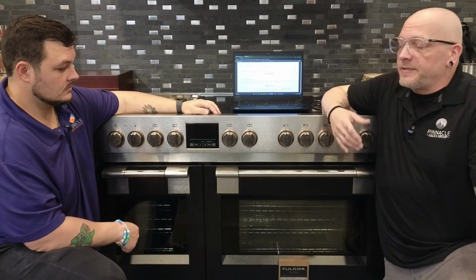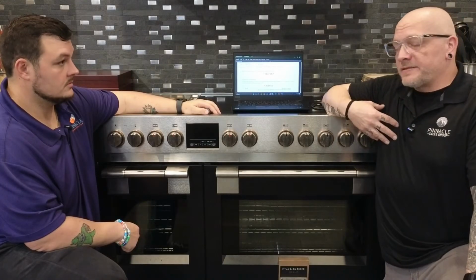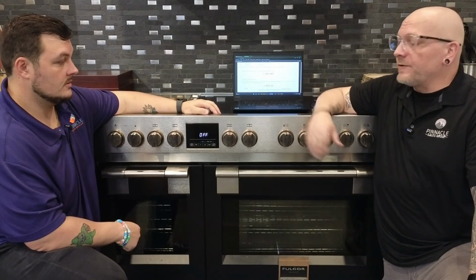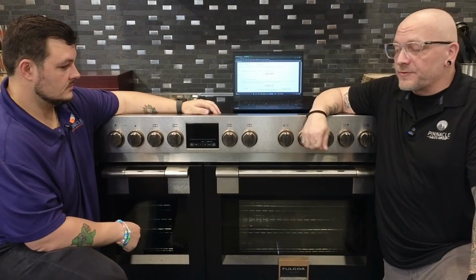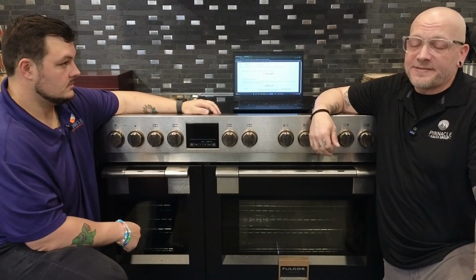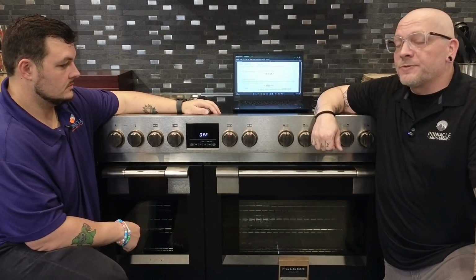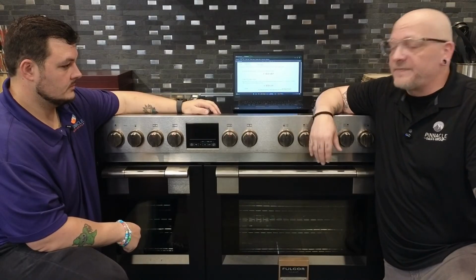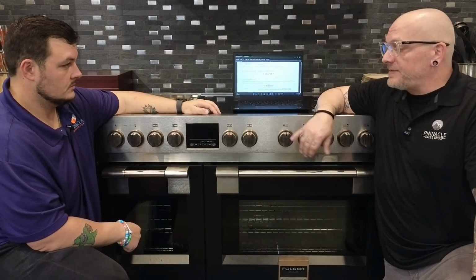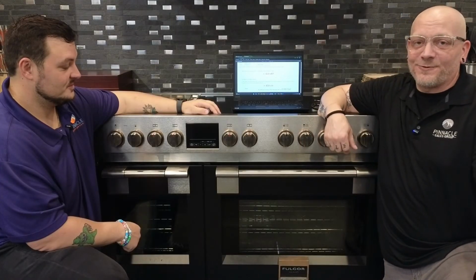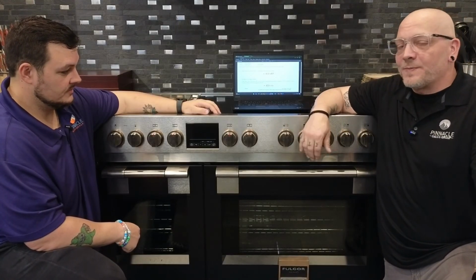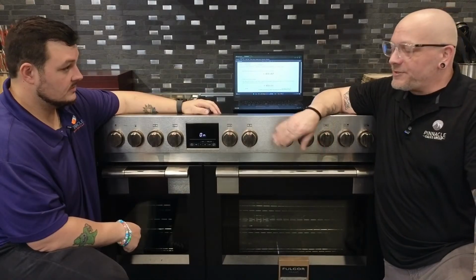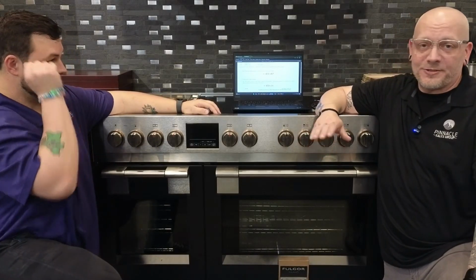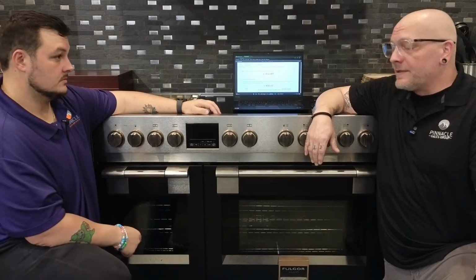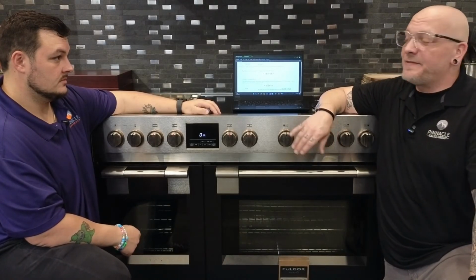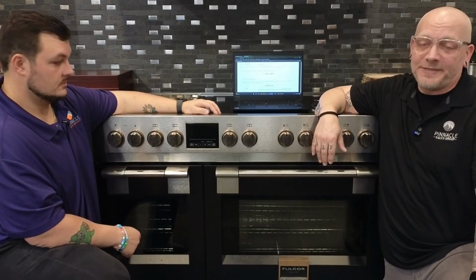Using this test is a great resource. Being a technician for over 25 years, pulling out a 48-inch range to put my meter on the terminals for that temp probe just to ohm it out and check the resistance, when this machine can do it for me with a couple buttons, is a lifesaver. Save your knees, save your shoulders, save the customer's floors, save the product. Just push a couple buttons and see what the temperature is reading. If it points you in a direction and you're way off one way or another, then go toward the temp probe, but don't head there first and pull the machine out if you don't absolutely need to.